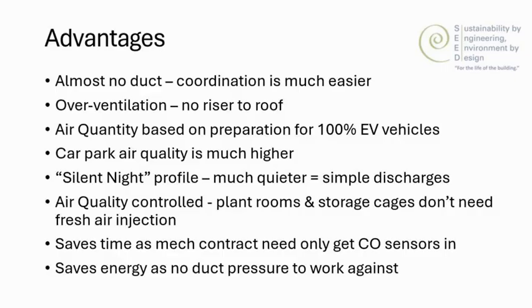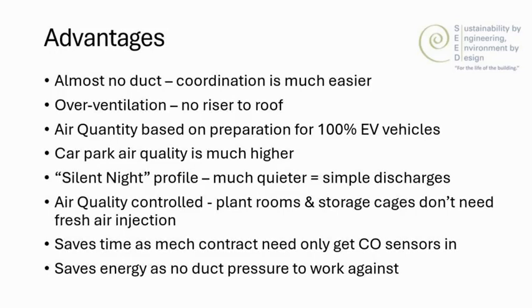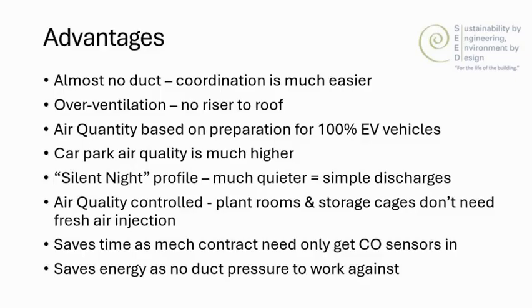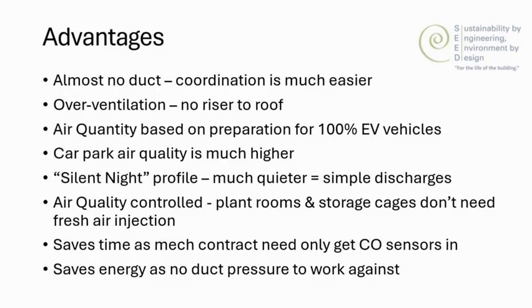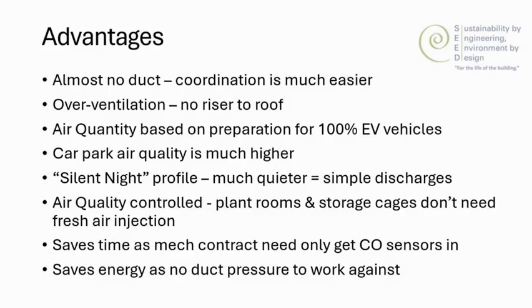The air quality within the car park is much higher. We use something called the silent night profile to have a much quieter and simpler array of discharges. The air quality is carefully controlled, so plant rooms and storage cages where we've got transient populations no longer need fresh air injection. We're saving time because the mech contract really just needs to get the cables in for the CO monitoring, and we're saving energy as the ductwork pressure is significantly reduced, so the fan sizes can also be reduced.